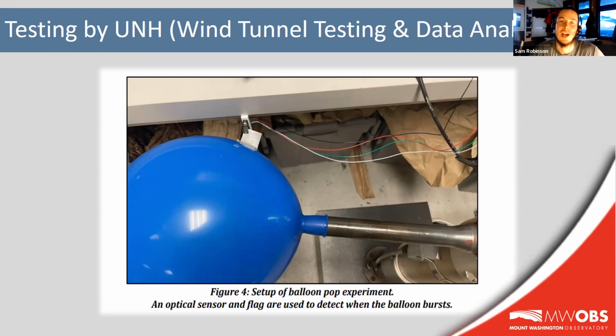So I'm sure some of you or most of you may be wondering, okay, what does all this mean in terms of the accuracy and performance of the actual instrument? The engineers at UNH explained to us that the step input from the balloon pop provided a measure of the worst case overshoot. And in the real world and in practice, wind speeds should not change so suddenly. And this just means that the diaphragm of the pressure sensor would not experience such a sharp acceleration and therefore would not overshoot. And they also explained to us that the settling time is much shorter than our 1 second average wind speed that we record, and then also the 200 millisecond sample period that we currently use. So therefore, this underdamped nature of the sensors will likely not produce error in the reported average data. In other words, these characteristics of the omega pressure transducers are not of concern to wind gust accuracy.